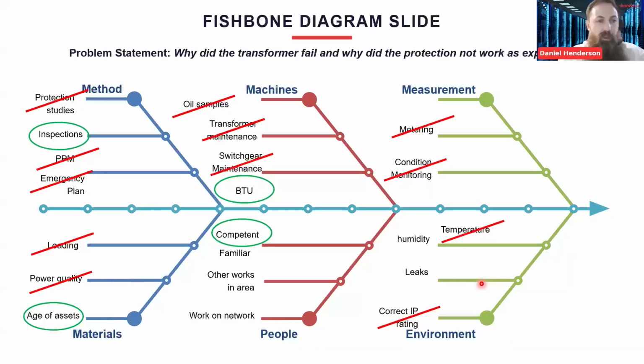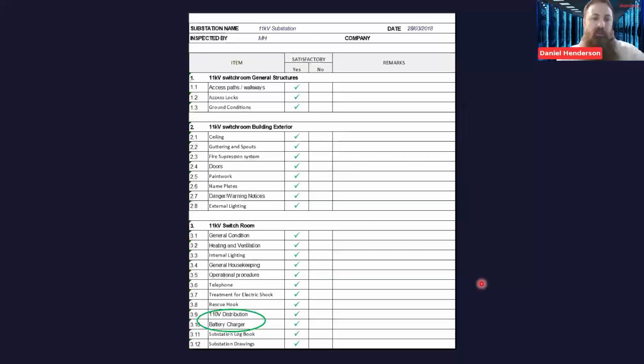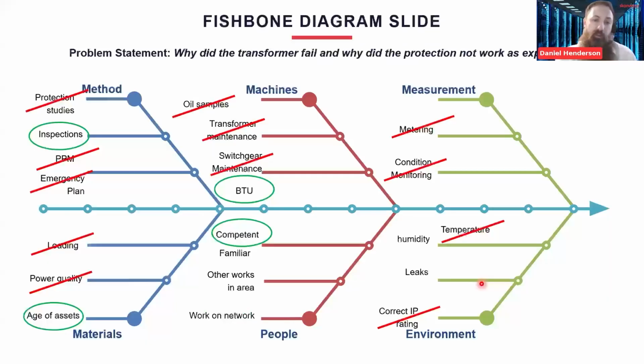Yeah, so on those inspections, it's a visual. They'll have a look at the batteries, and I think they'll check the float voltage. So they check the 110 on the test function on the batteries that were there. To confirm, the tripping circuit wasn't tested; that doesn't form part of the battery maintenance. On the maintenance, they just tested the output from the batteries.